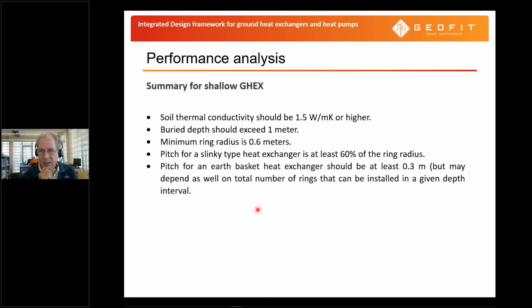So for shallow ground heat exchangers, we can have these types of conclusions. The soil thermal conductivity should be around 1.5 watts per meter Kelvin or higher. If you don't do that, you have a bigger effect on the performance. The buried depth should be at least 1 meter. The minimum ring radius is around 0.6 meters. The pitch for a slinky type heat exchanger, at least 60% of the ring radius. And the pitch for an earth basket spiral type heat exchanger, at least 0.3 meters. Okay.